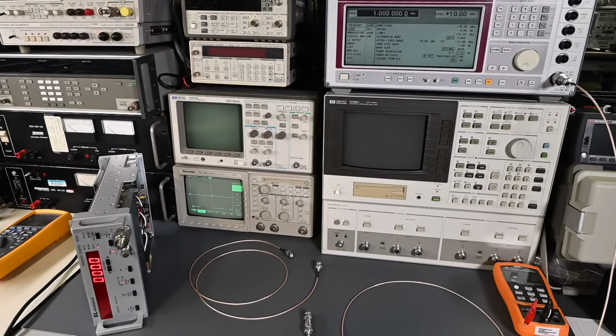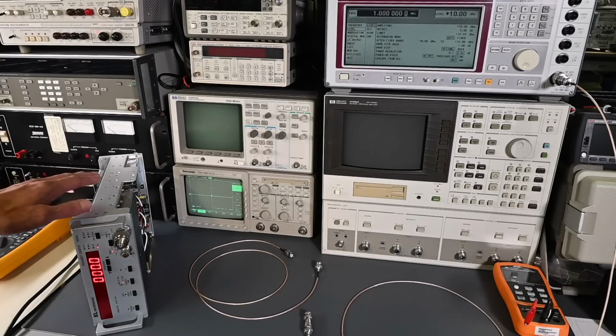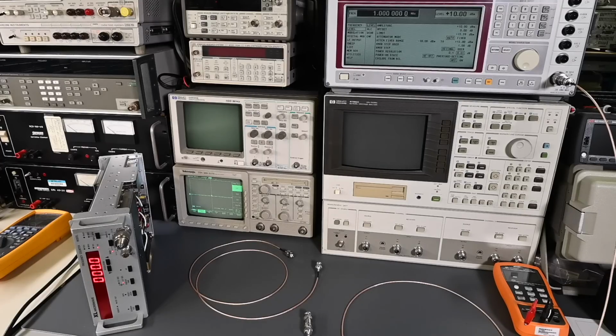So I spent some time going through the frequency counter's various functions. Now I see what the problem is, so let me show you what's going on. So the first thing that I checked is the internal time base, or the reference oscillator. It's supposed to be right at 10 megahertz, and it's very close to that value. It's not wildly out of spec. It's perfectly fine the way it is to do these initial tests, but it needs a little bit of a calibration, a little touch up, and I'll definitely do that.